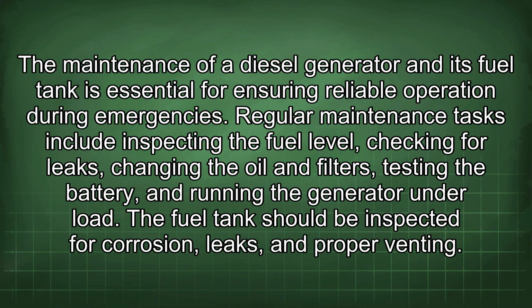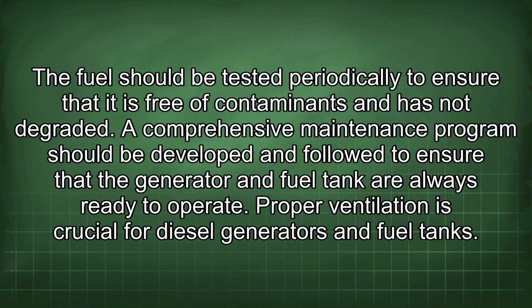The maintenance of a diesel generator and its fuel tank is essential for ensuring reliable operation during emergencies. Regular maintenance tasks include inspecting the fuel level, checking for leaks, changing the oil and filters, testing the battery, and running the generator under load. The fuel tank should be inspected for corrosion, leaks, and proper venting. The fuel should be tested periodically to ensure that it is free of contaminants and has not degraded. A comprehensive maintenance program should be developed and followed to ensure that the generator and fuel tank are always ready to operate.